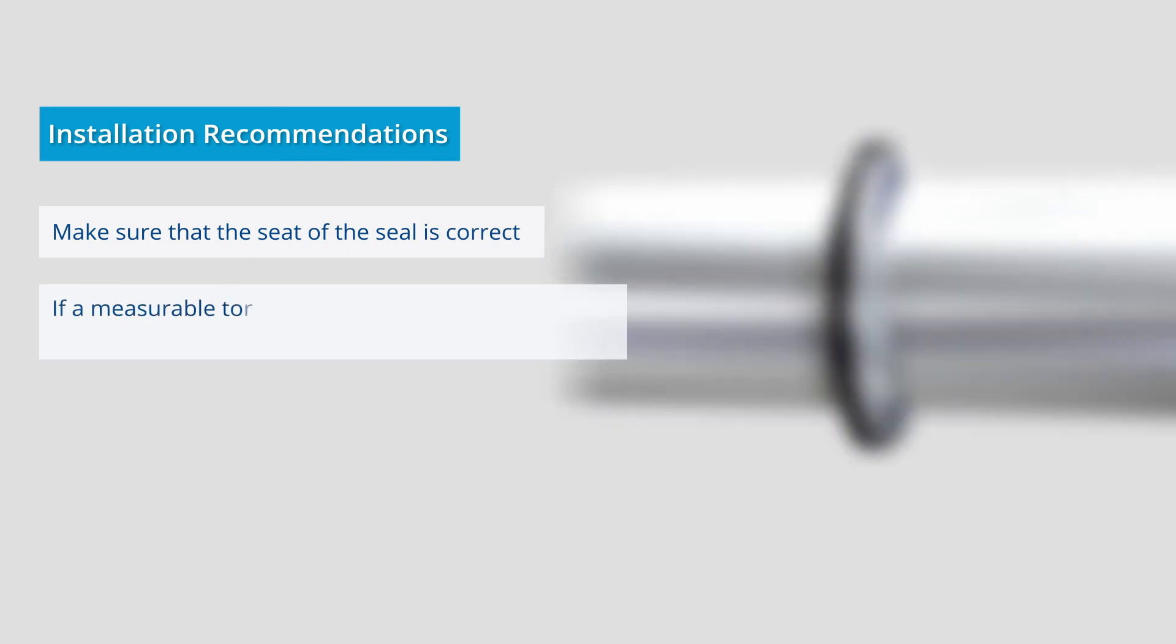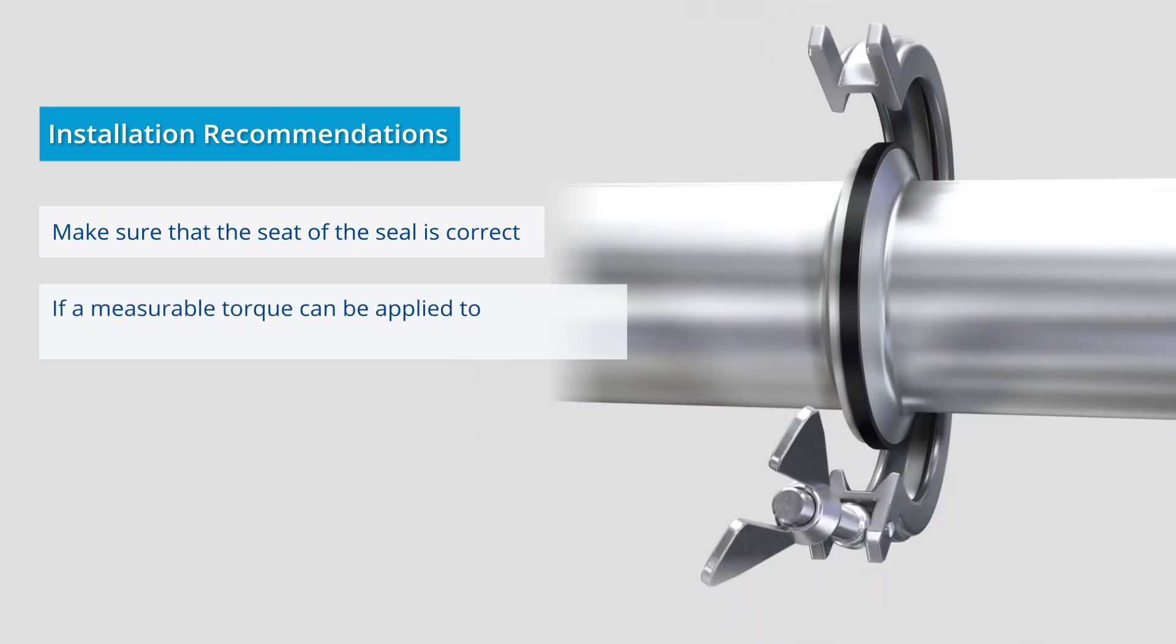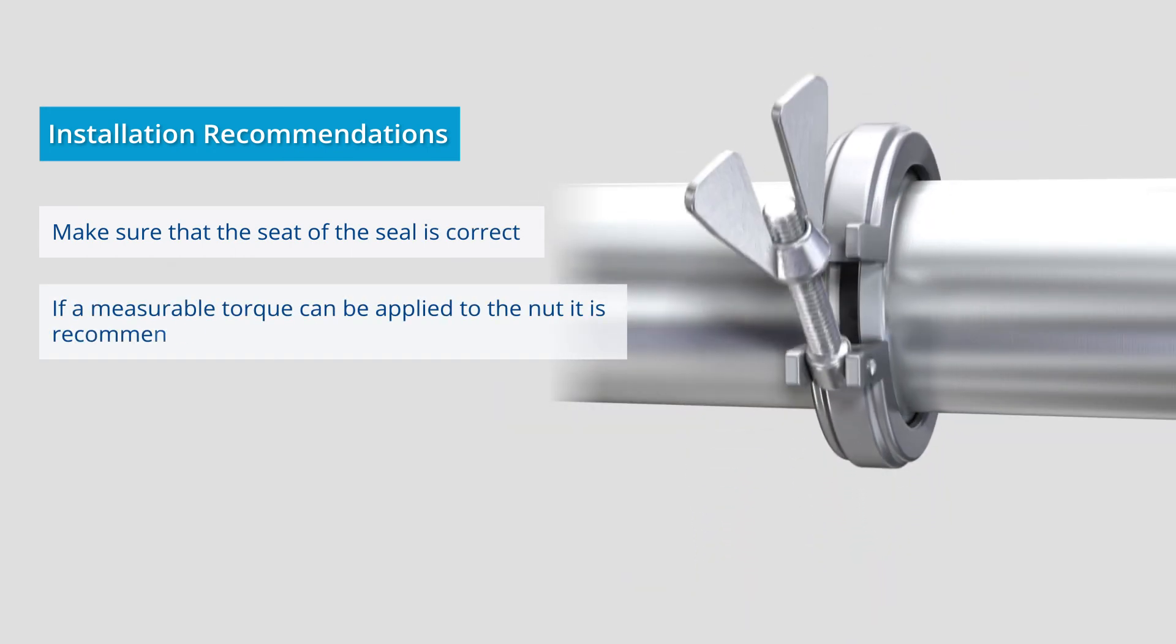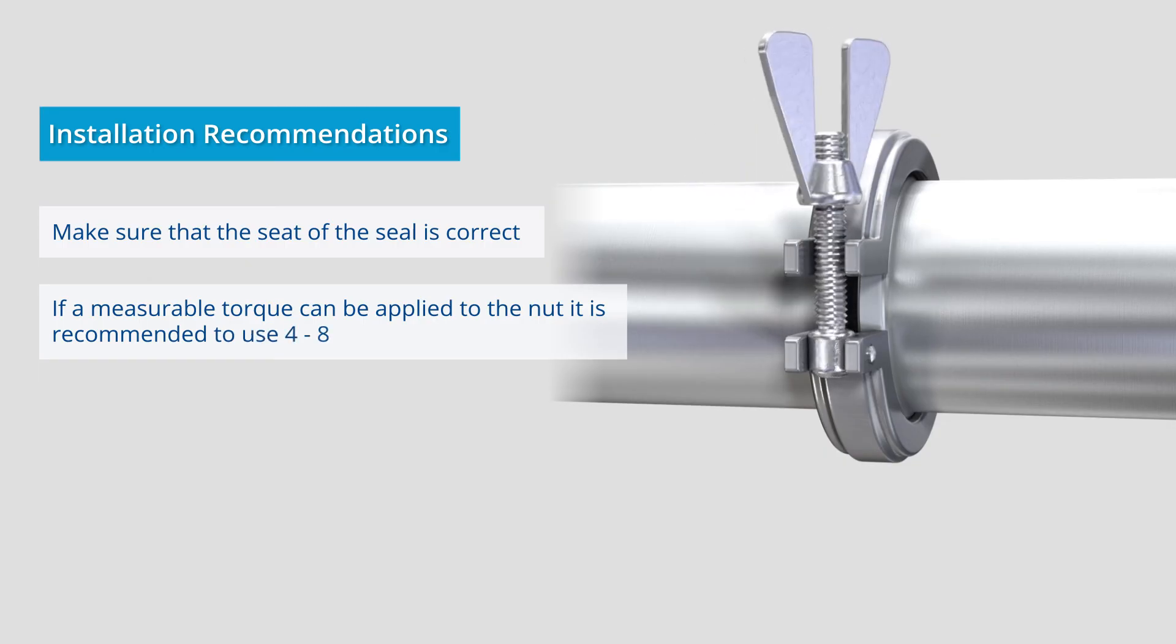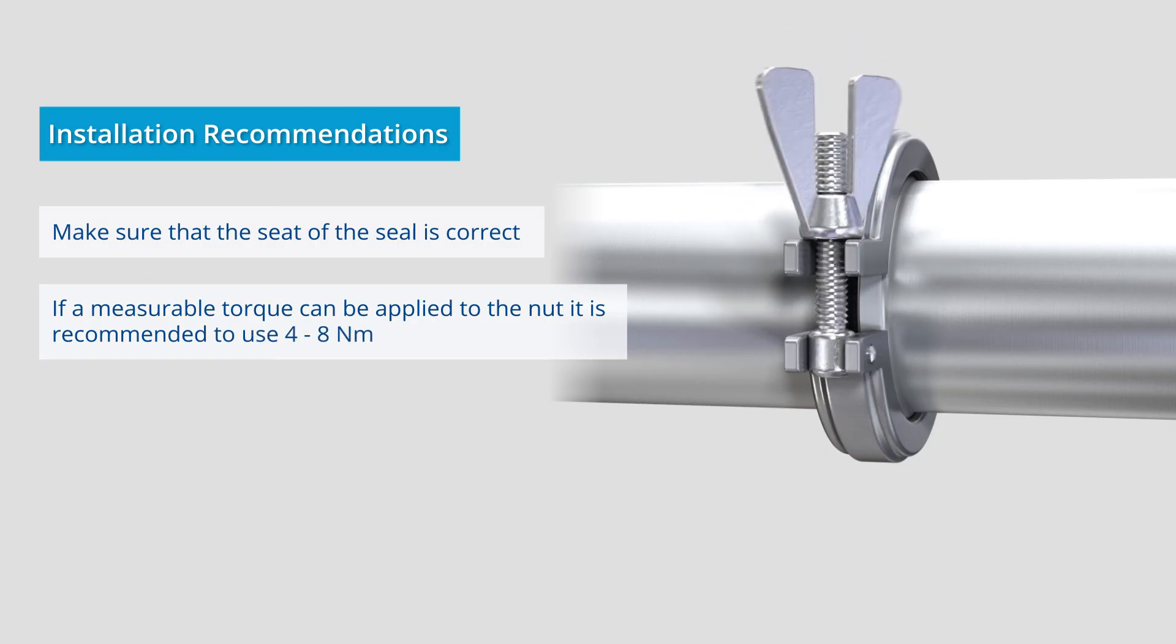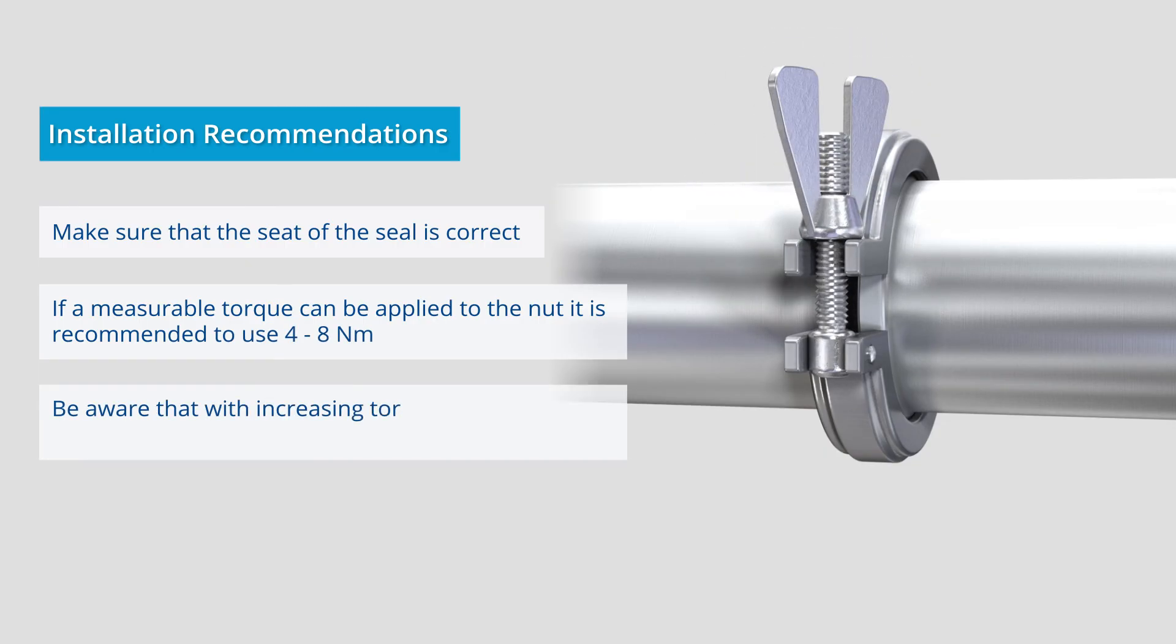If it is possible to apply a measurable torque to the nut, 4 to 8 newton meters is recommended. Note that the sealing edge may move toward the center of the pipe as the torque increases.